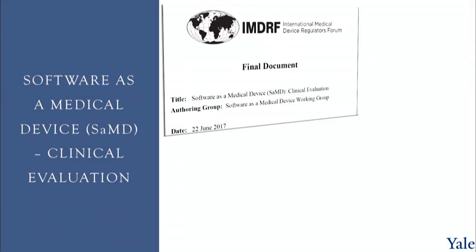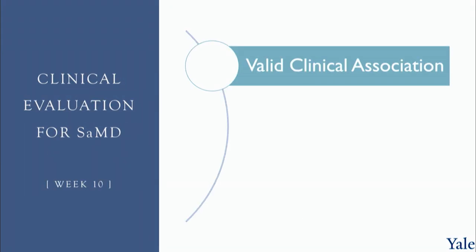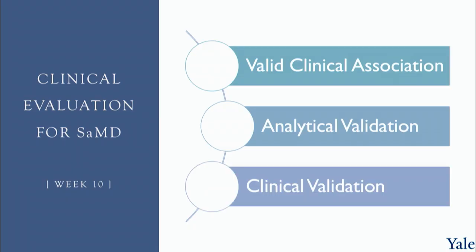A third IMDRF document, to be covered in more detail in week four, is the guidance on quality management systems, describing the characteristics for SaMD. The fourth document is on clinical evaluation, issued by the IMDRF in June 2017 and reissued by the FDA a few months later. It covers three components: valid clinical association — is the software output relevant to the disease; analytical validation — is the output accurate; and clinical validation — is it helpful, and can it improve patient outcomes.